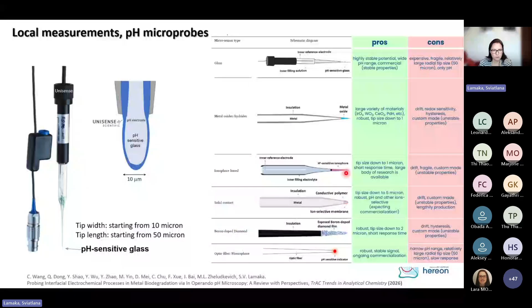Similar to this, an amperometric Clark type microprobe sensitive to the concentration of dissolved hydrogen. Again, very small tip size, stable signal. The difference is that there is a platinum anode inside that is biased positively, and there is hydrogen oxidation, and the oxidation current is recorded.